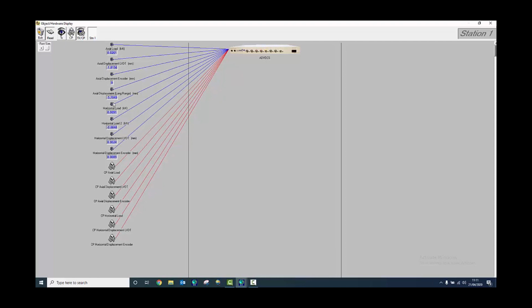So if we look at 3 transducers that read our displacement, which is axial LVDT, axial displacement encoder, and axial displacement long range, they should all move now by 1 millimeter in the positive direction. So as you can see, they all change by 1 millimeter. We move it 2 millimeters. So it seems like all of our axial displacement transducers are reading correctly.